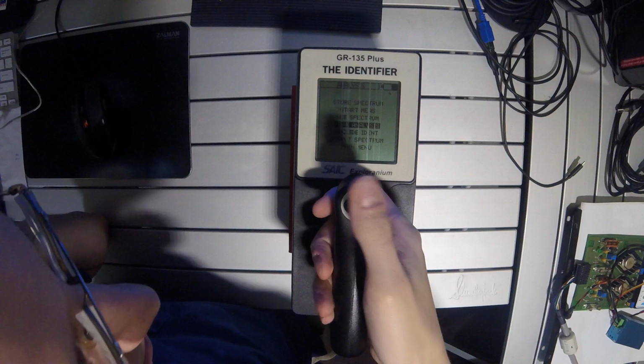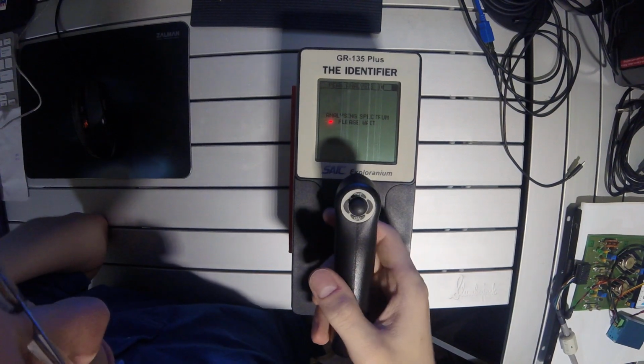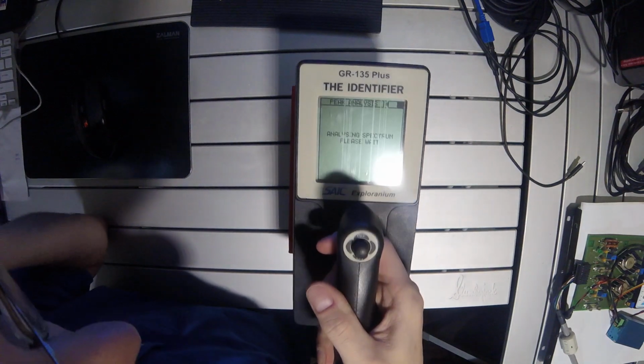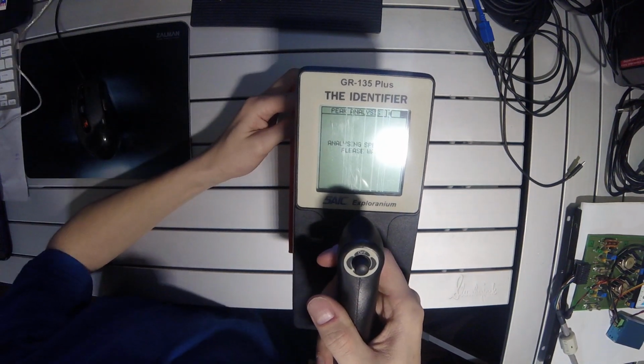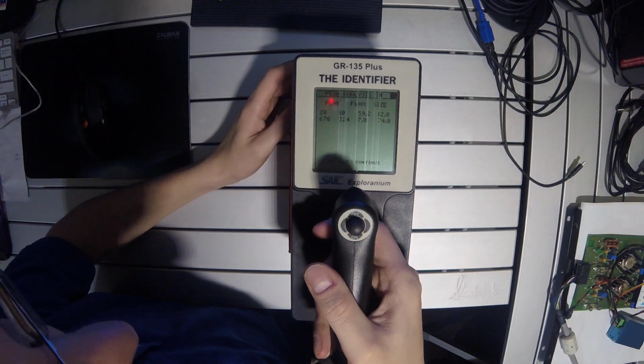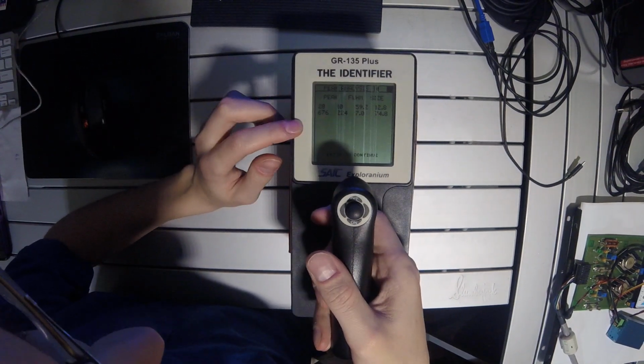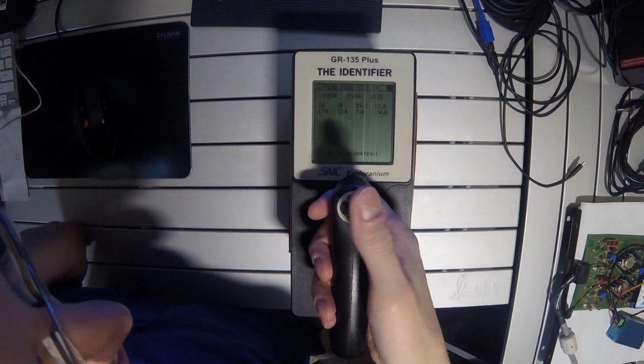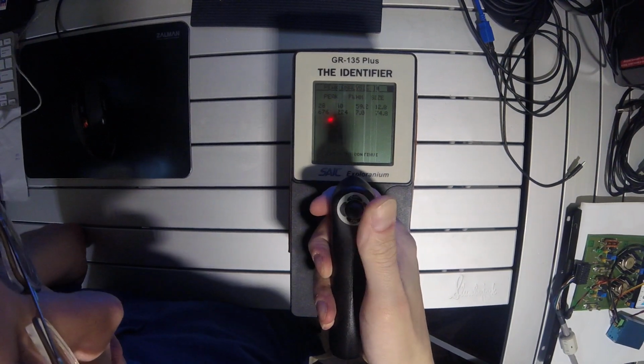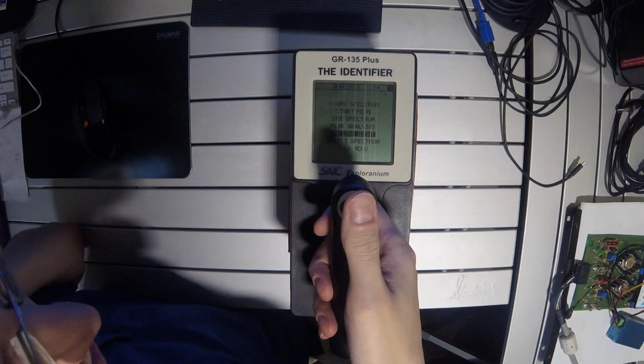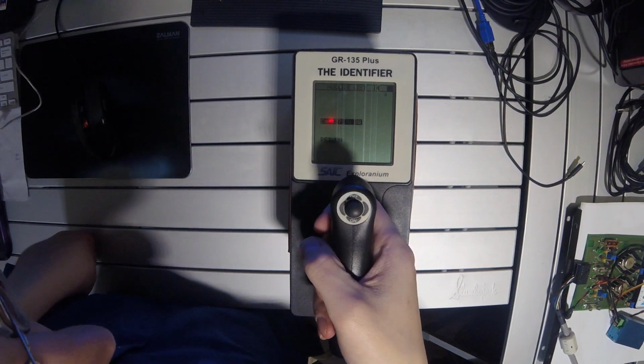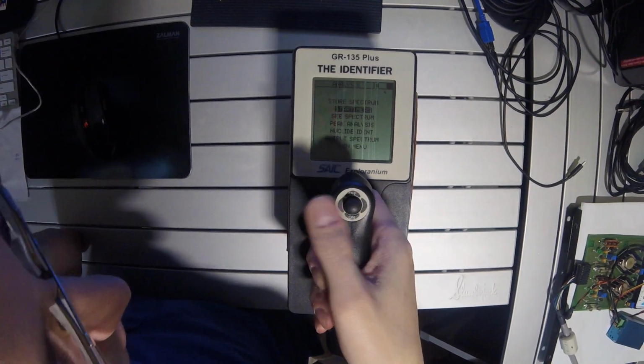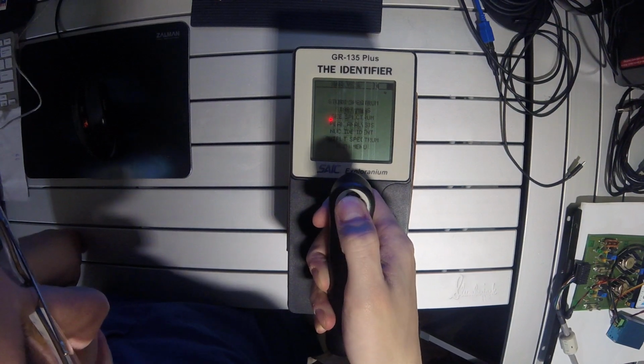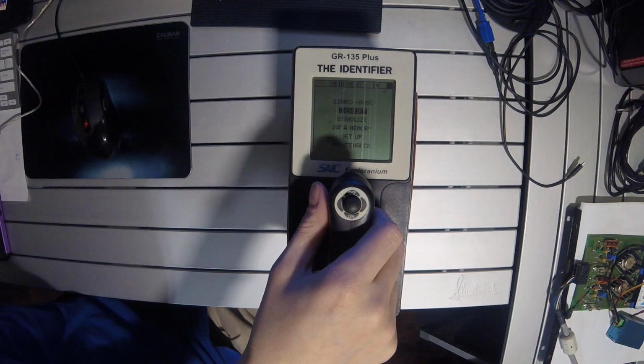So we'll go to peak analysis. This is analyzing spectrum, please wait. And it's reading out 676 keV main peak, so that's not too bad. Next, we'll go to nuclide identify, and there it has it, cesium-137. So that's for one isotope.